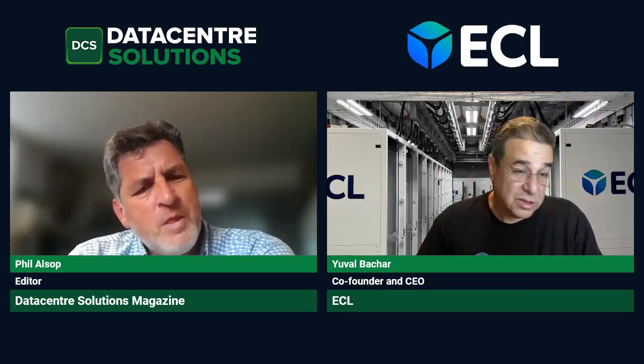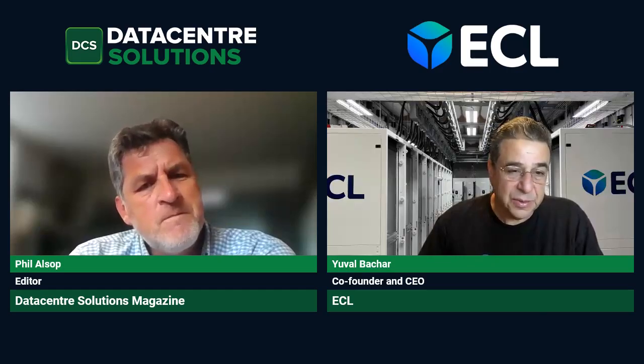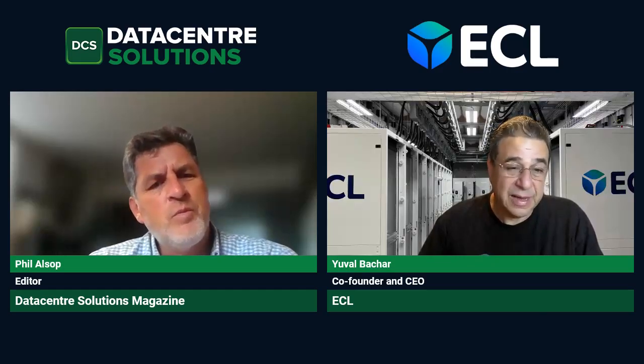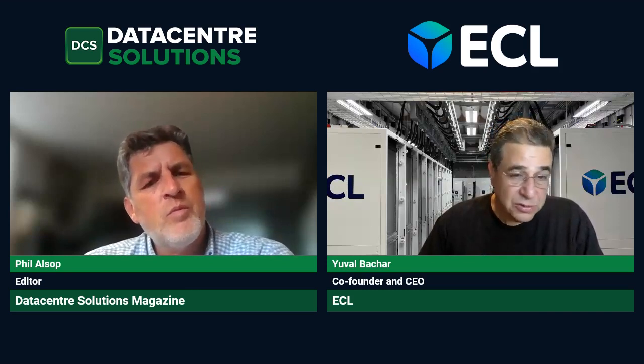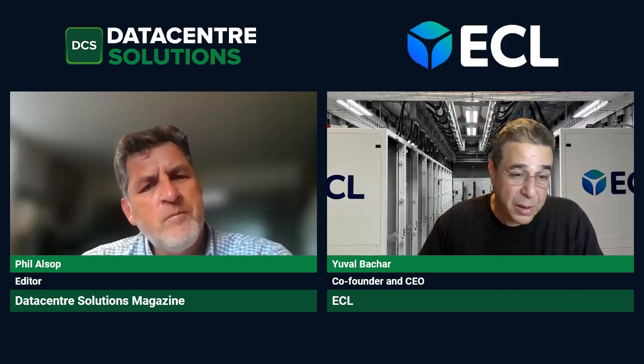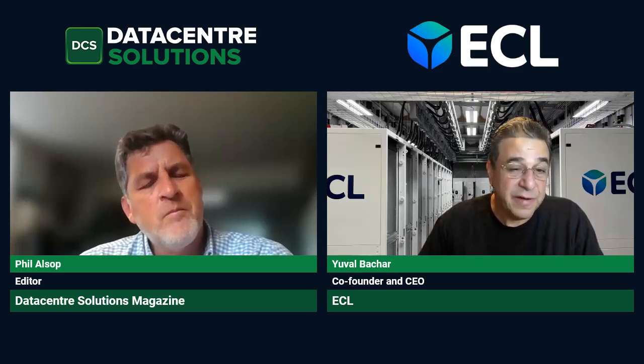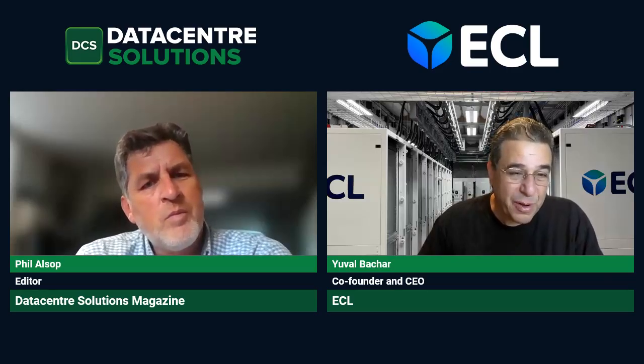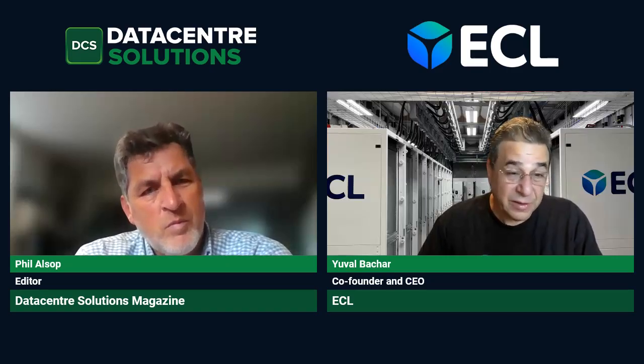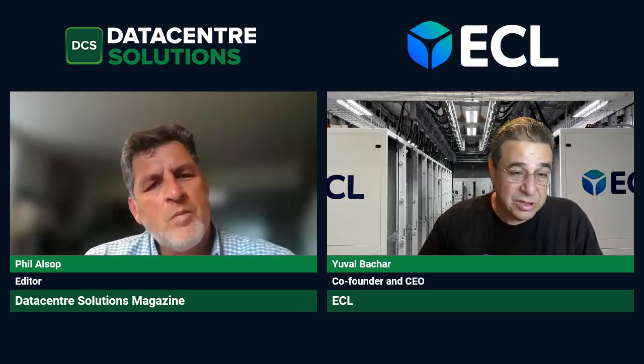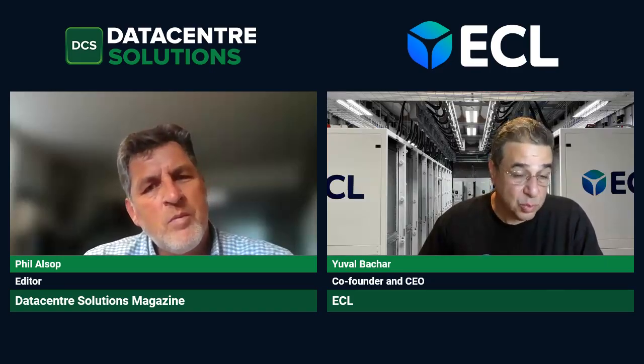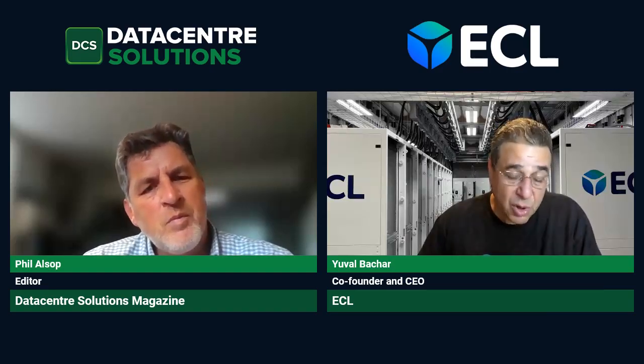Our market isn't necessarily just AI. We do very high density racks, so we can operate very well in an AI environment. But for some customers using more traditional compute, they ask for lower power per rack, they don't need 50 to 75 kilowatts, they need 25 to 30. We use exactly the same modular block, just put more racks in there and reduce the power per rack. We don't need to change anything in our technology for generation, cooling, or anything else. Our target for the blocks is dedicated, we do build to suit. So if a customer wants 25 to 30 kilowatts because they're using standard servers, they get exactly the same block, just with more racks so they can put more servers in.